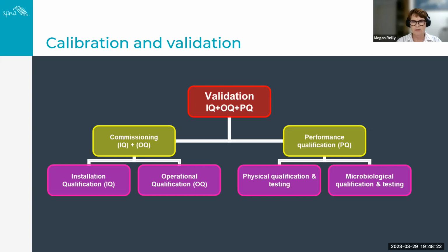So if there are any changes in the items or the types of instruments that you reprocess, you might introduce a new surgical procedure into the practice that requires you to use different instruments, and if that creates a greater challenge to your previously validated items, it needs to undergo validation. Installation qualification provides assurance that the equipment and its connected services, so the water and the drainage, comply with a specific set of specifications, and it's safe and fit to use. Your operational qualification provides assurance that the equipment functions correctly to a set of performance criteria. And your performance qualification demonstrates that your equipment is capable of processing the load.